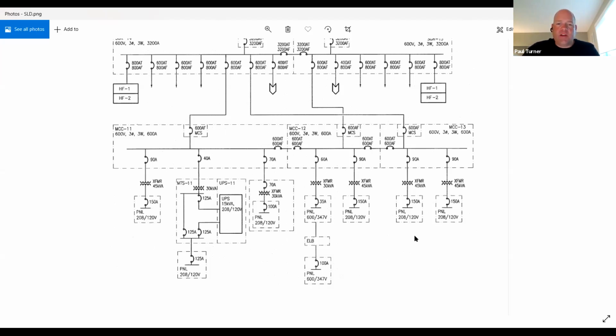Now, a few other aspects of this system are at the 600 volt level. We have these high frequency filters. These are harmonic filters that stabilize the 600 volt power as equipment is being switched in and out. There can be spurious voltage levels on the systems, and these filters help to stabilize that power to keep it consistent and stable. We also have a UPS, an uninterruptible power supply, that is fed from 600 volts normally.